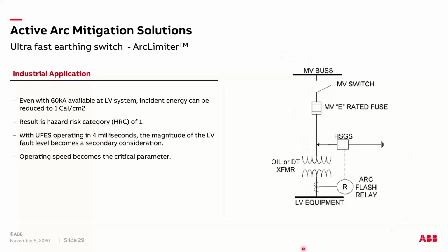In that scenario, when we install an arc flash relay with a high speed grounding switch or a UFES on the primary side of the transformer, if you have an arcing fault on the low voltage equipment, the arc flash relay in conjunction with the high speed grounding switch will transform that arcing fault into a three-phase bolted fault on the primary side of the transformer, which will be cleared by your upstream fuse in 1 to 2 milliseconds. Because of this three-phase to ground bolted fault, the clearing time of your E-rated fuse is really fast, and it's going to melt much faster and much quicker.